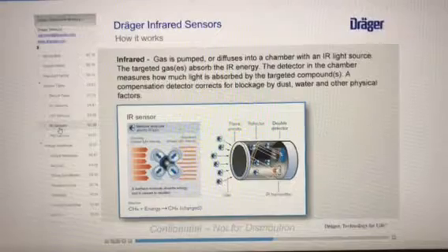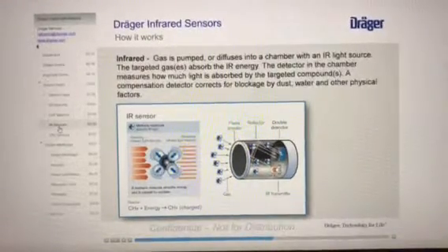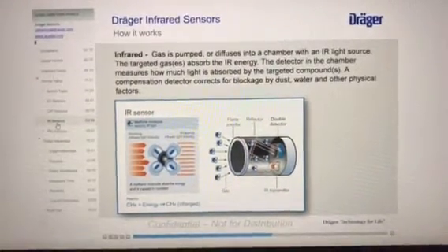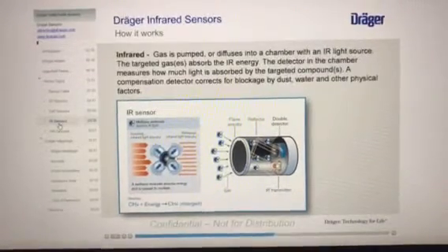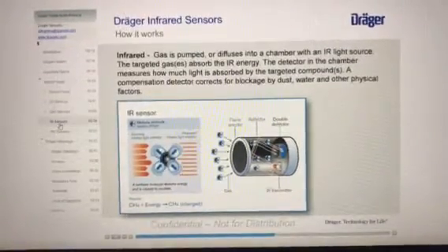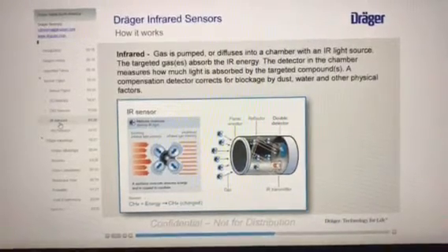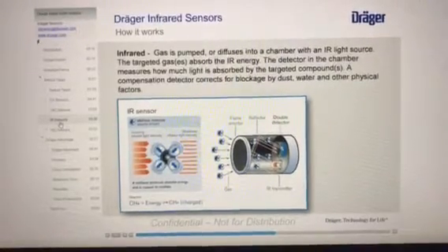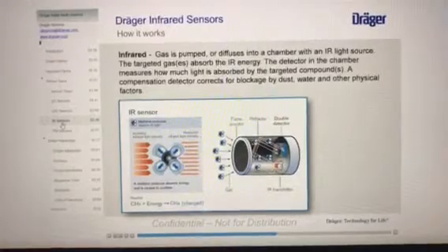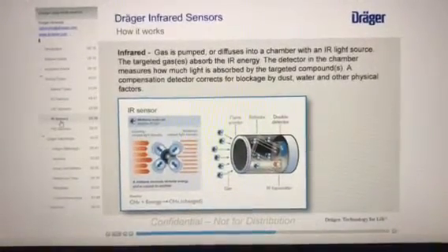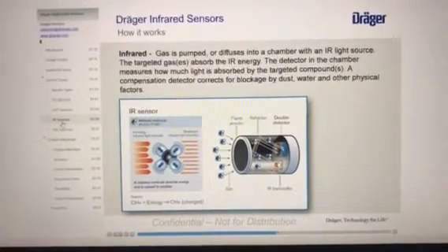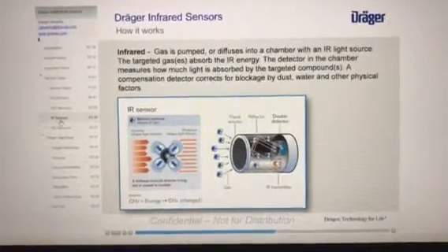Gas enters the sensor chamber through the filter screen. If hydrocarbons are not present, the infrared light will maintain its intensity. If hydrocarbons are present in the air, then the infrared light becomes weaker. The intensity drops in relation to the concentration of the hydrocarbon, for example, methane. The double detector converts the reading from light into an electric signal that is read by the monitor.